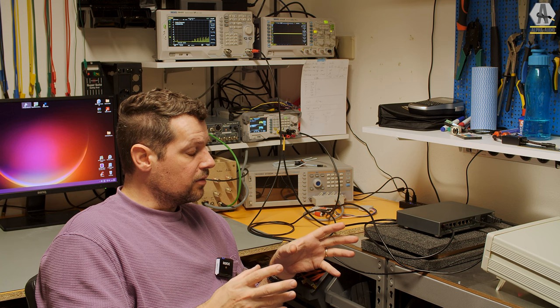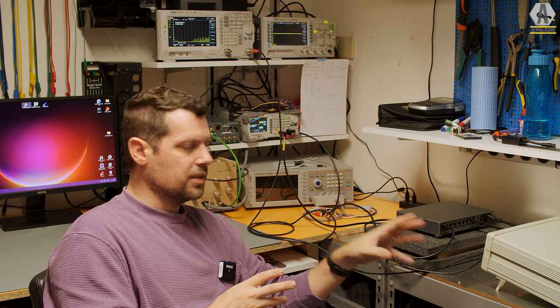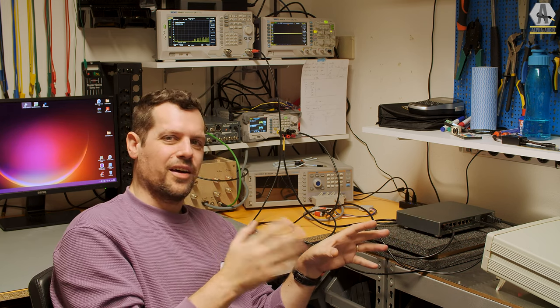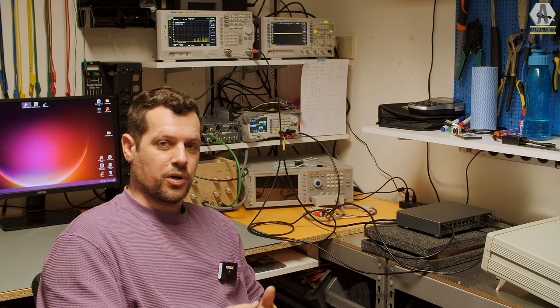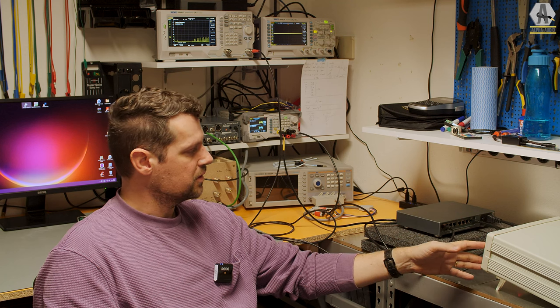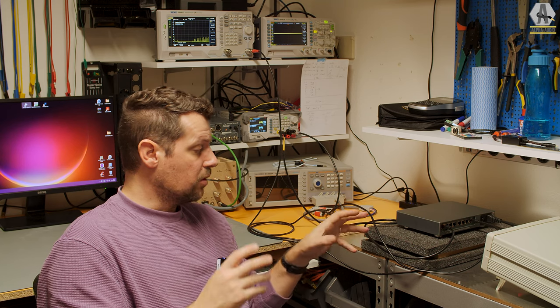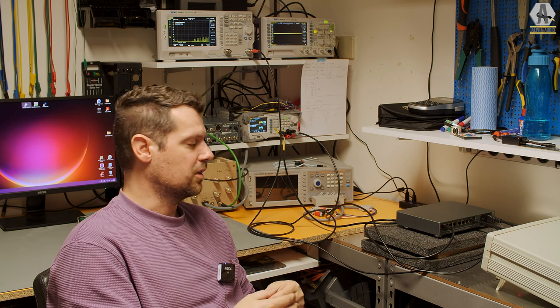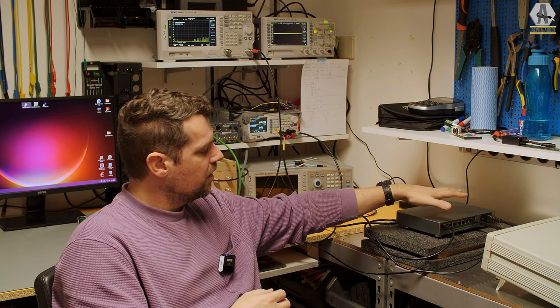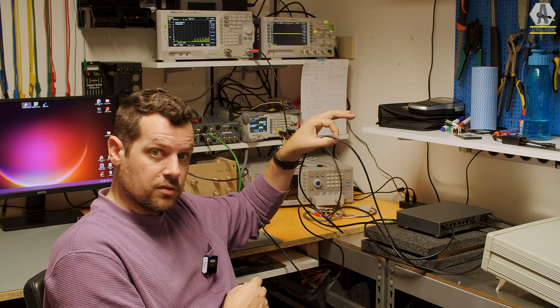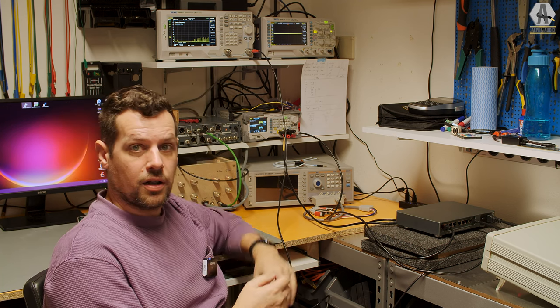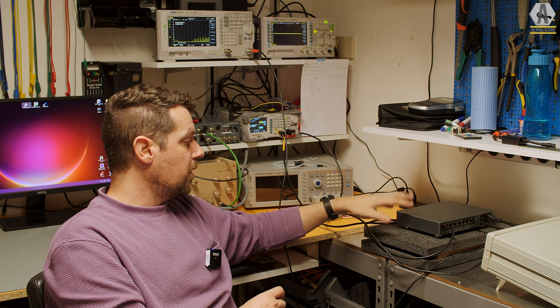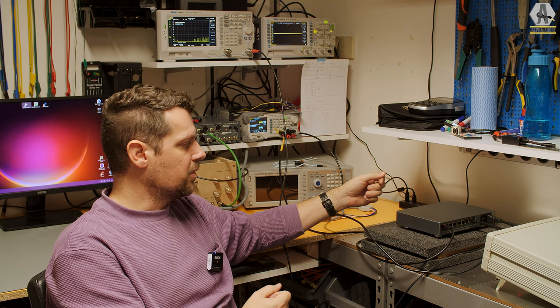Well, recently, sorry, we bought a Tekbox LISN device. And it's not listening like listening, but a line impedance stabilizer network. And what you can do with that is, well, of course you can do EMC pre-compliance testing. It's built for that, but we are measuring power line noise. Conducted noise. So no radiation noise or EMC. Well, it is EMC noise, but we measure the power supply from the device under test, the DUT. And the listen device filters out the noise, so to say, and puts it into a spectrum analyzer. So we can see how the power supply performs in the device in terms of noise.